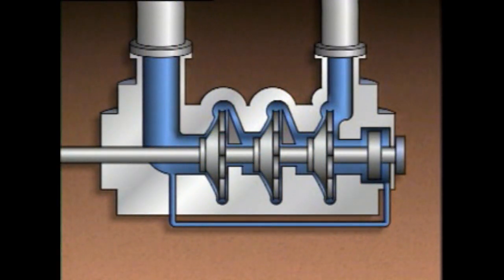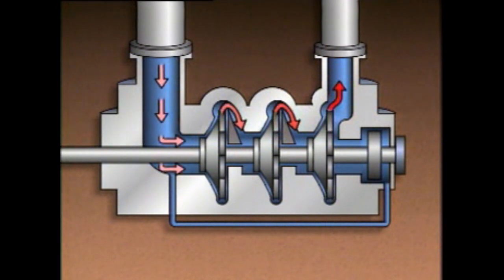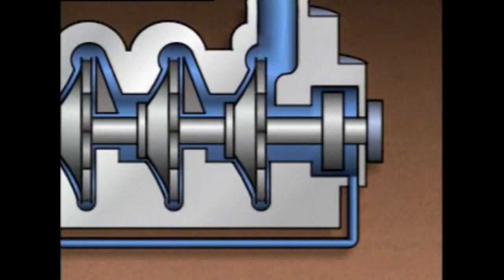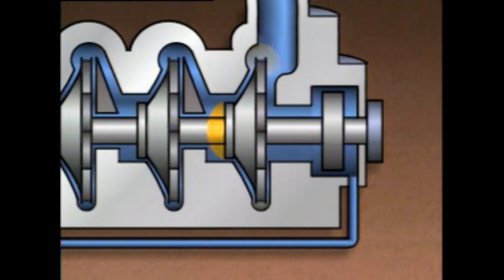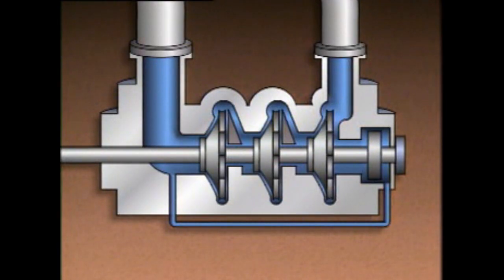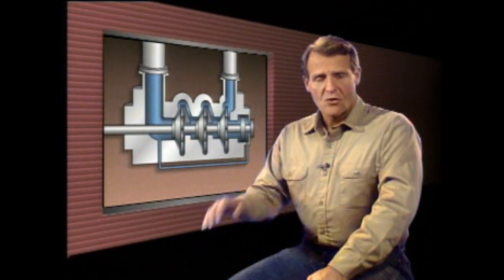Regardless of how impellers are arranged or how many stages a pump has, the liquid's pressure increases as it passes through each stage. This creates a thrust across the impellers known as axial thrust, caused by the pressure difference between the suction eye and the volute. Axial thrust tries to push the pump shaft toward the suction eyes. To allow the pump to operate properly, this thrust must be offset — either by a thrust bearing, a balance piston or balance drum, or by the arrangement of the impellers.